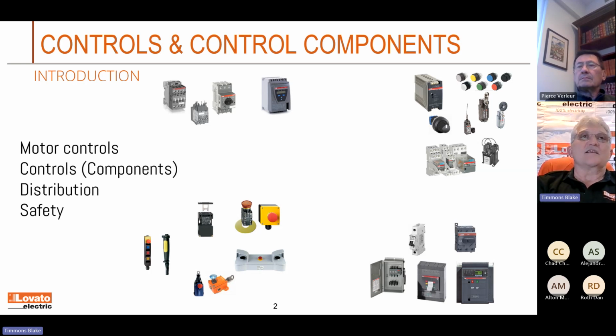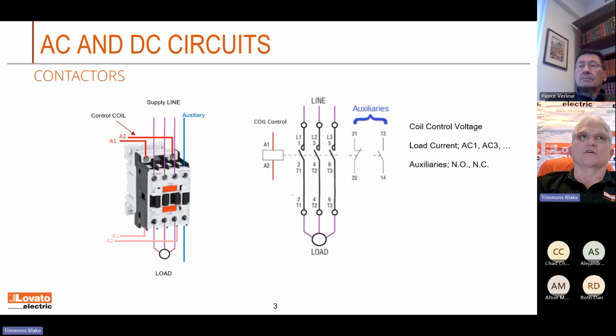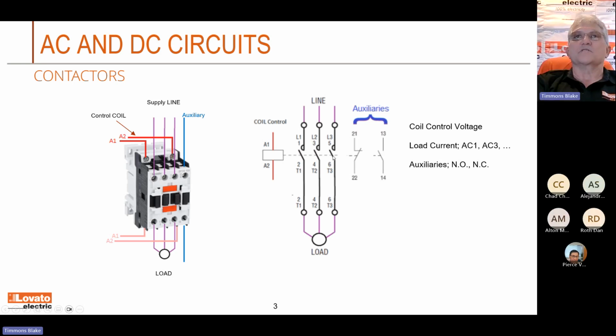So with that said, I always like to start with the motor starter, what it consists of. A lot of people don't realize what a motor starter does. We're passing part numbers back and forth a lot, and they don't realize that all it is is an electromagnetic switch. But you've got three things you're switching, one for each leg of a three-phase system. As you can see in the drawing, in the middle you've got your line coming in, and you can see the three switches. And you can see off to the left the coil that switches those things in.